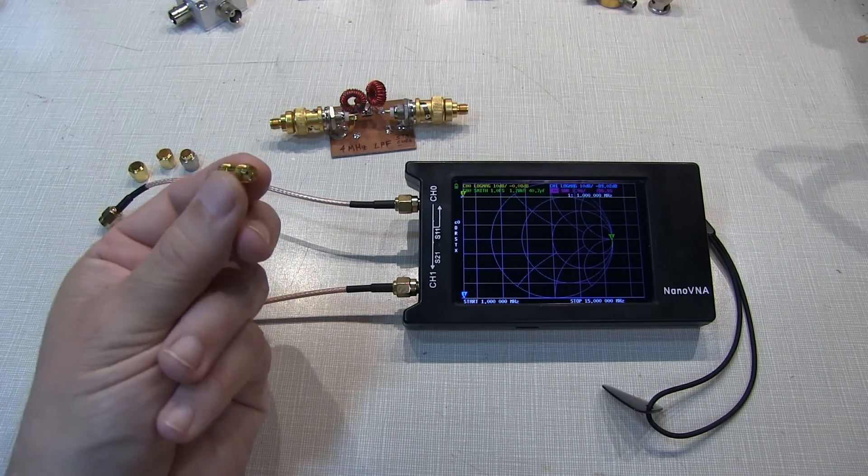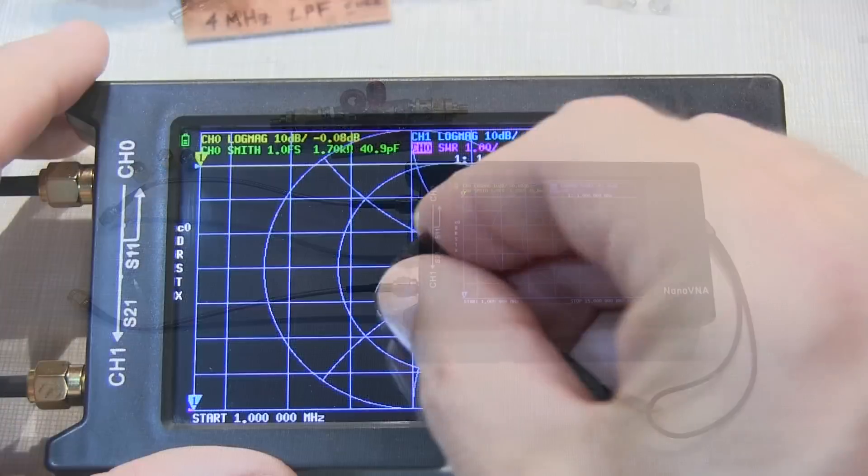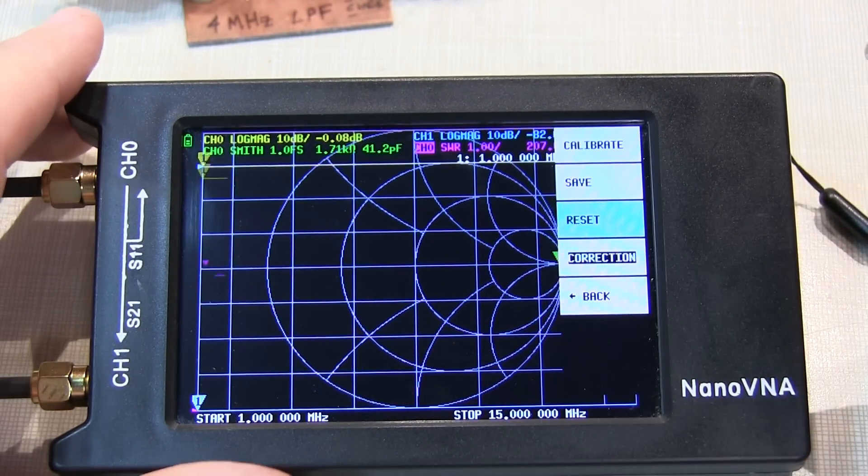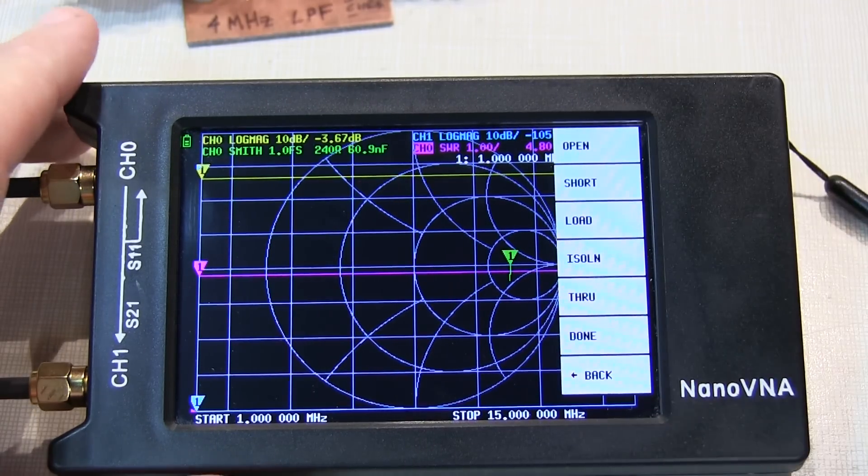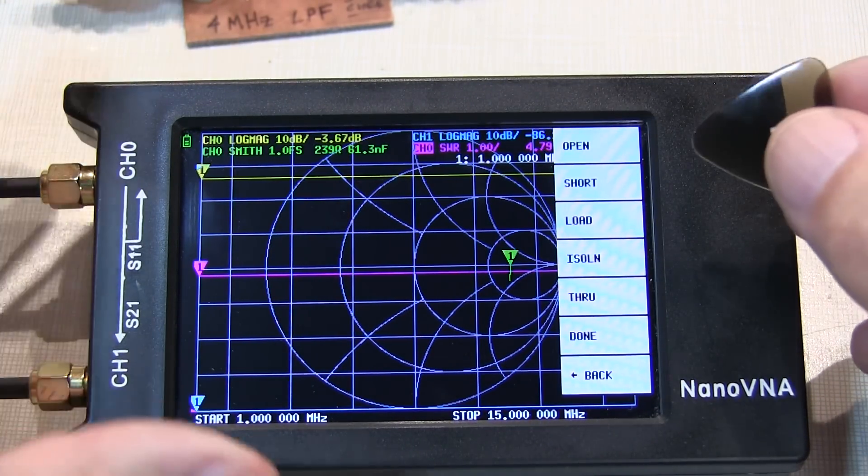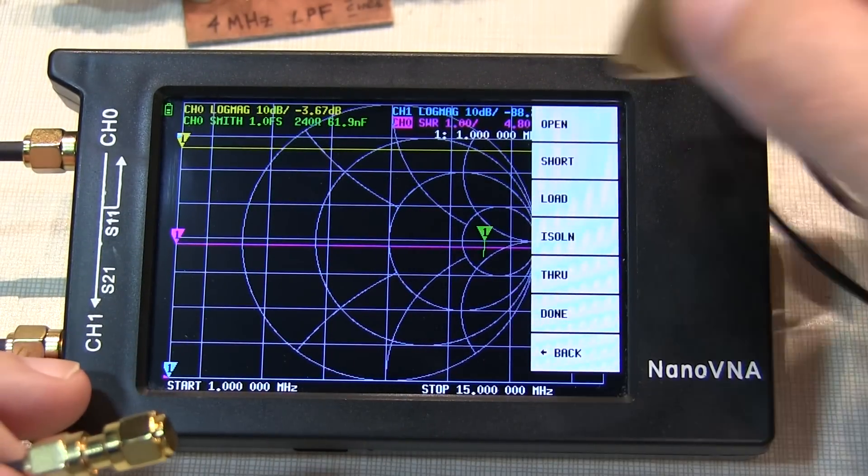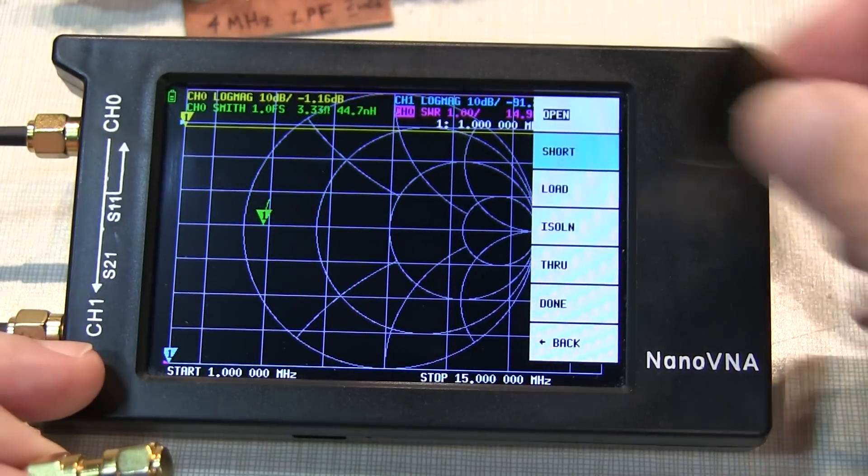We'll use this little SMA female-to-female adapter or bullet to connect our calibration standards to the end of the cable. So we go into our menu, and go back to the beginning, and hit Cal. We'll hit Reset to reset the calibration, and then hit Calibrate. Now in this case we're going to be making both a reflection measurement as well as a transmission measurement, so we need to run through all of these calibration steps. We'll start by connecting the open to the end of our cable, and touch open. Next, we'll connect our short to the end of the cable, and hit short, and then connect our 50 ohm load to the end of the cable. Hit Load.